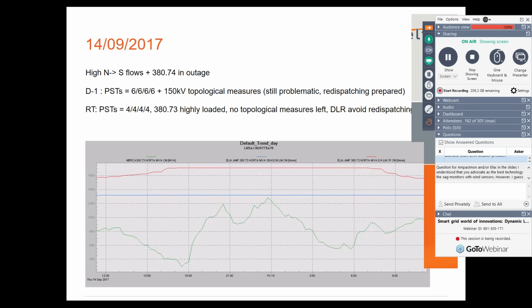And we also had to optimize the grid with all topological measures we could find. But we saw that in real time, so when the situation really happened, the lines were still really highly loaded. And because the PSTs were also reduced to their limits, the only way to go further was to pay for international redispatching, which means we had to pay the Netherlands to reduce the power plants and France to increase the power plants. This cost, for sure, without any calculation, $500,000 for this situation. This is a rough estimate, of course, but this is the most costly remedial action you can find.